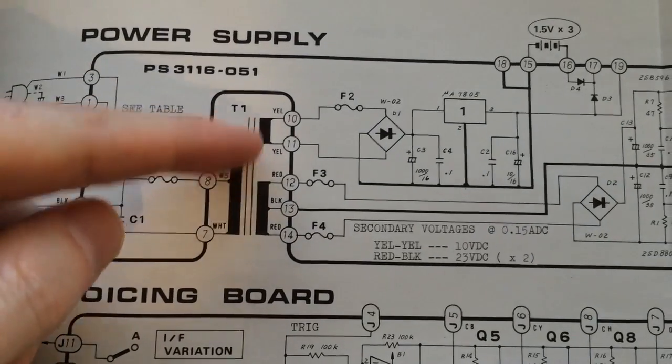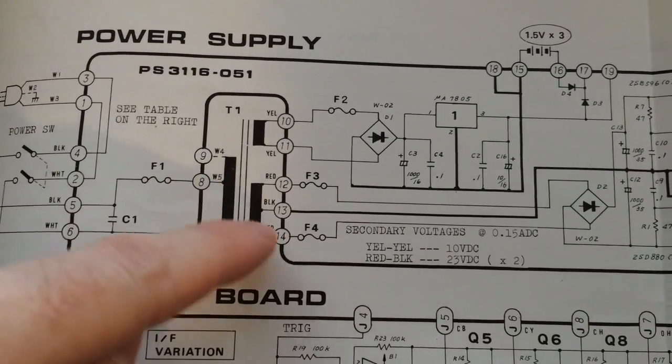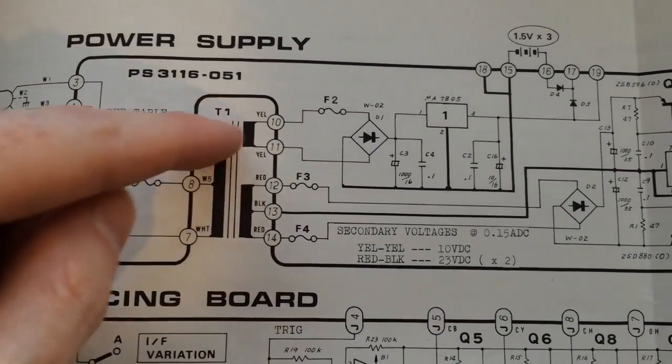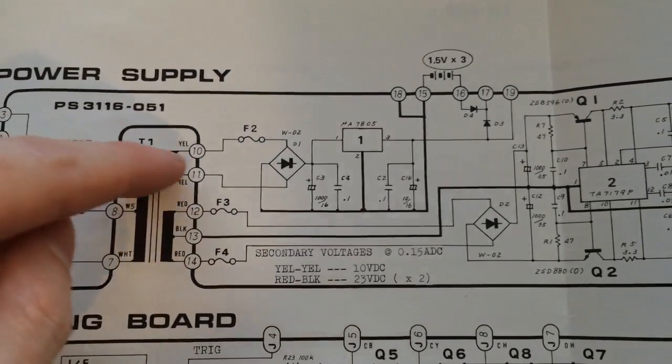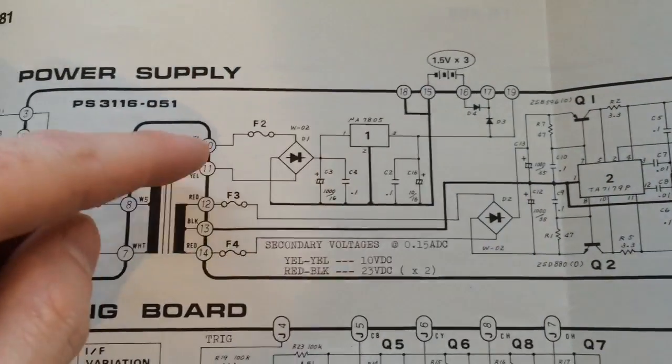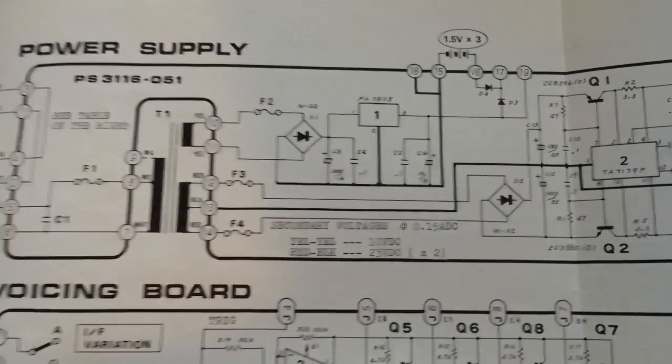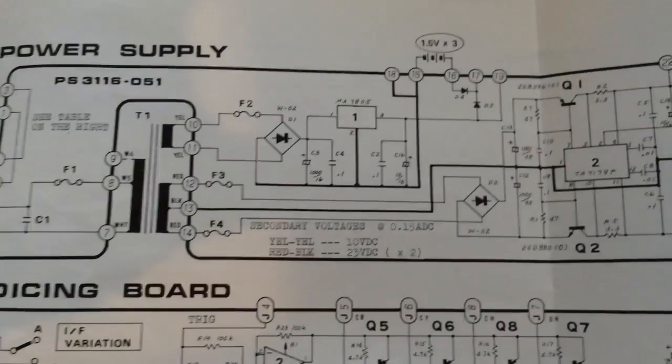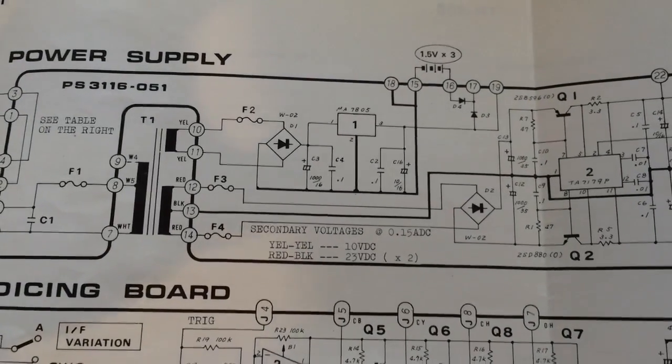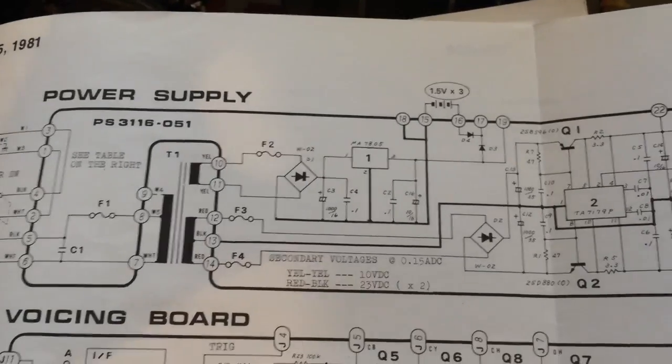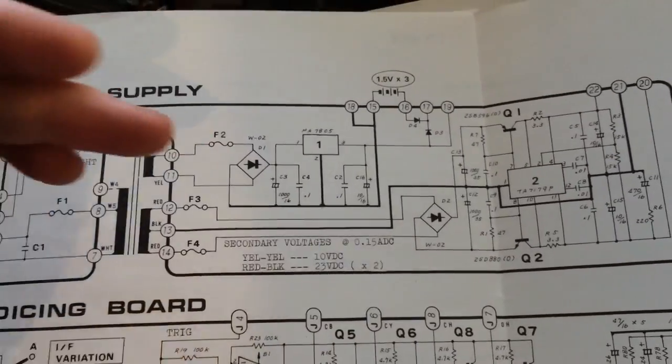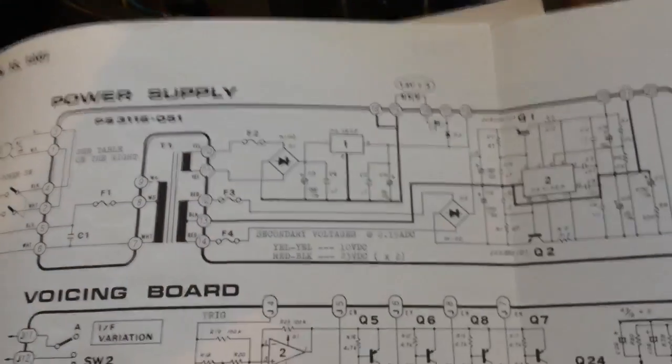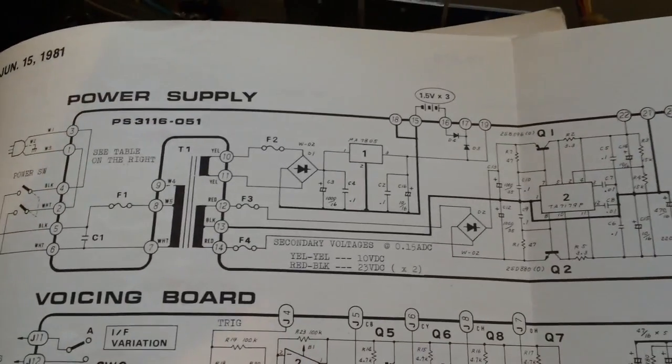If we have a look at the schematic, you can see here there's two completely separate windings. This one's multi-tapped, it's got a center tap, but the 5 volt, the one that's used to generate the 5 volts, is kept separate as if it's isolated from the rest of the instrument. That's not uncommon because the chips that run off 5 volts, the digital chips, they introduce a lot of noise onto the line.